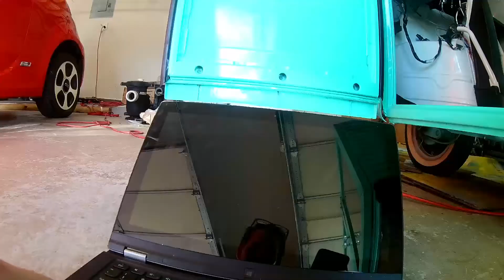So what's going on over here? Let's talk about it. Coming in nice and tight on these guys here. This is my charge controller, and this is the BMS, or battery management system. Together they operate through this CAN bus wire, which communicates and sends signals between the two about the battery's state of health, charging, and discharging. With this communications cable that plugs in right here, we'll run it to my computer and see what we've got. Fired up.